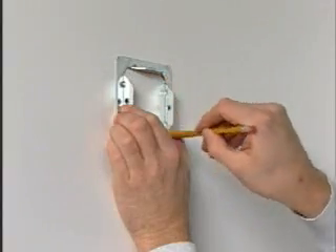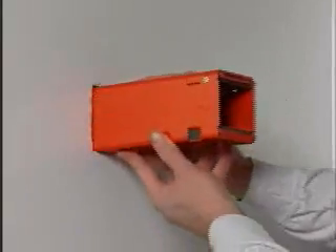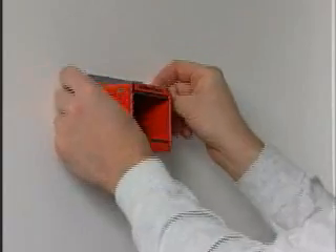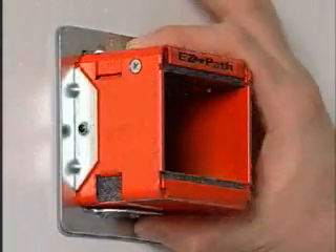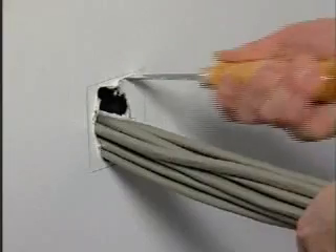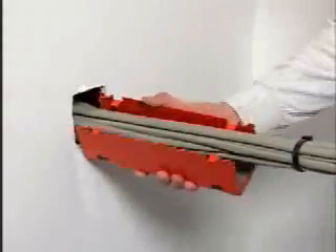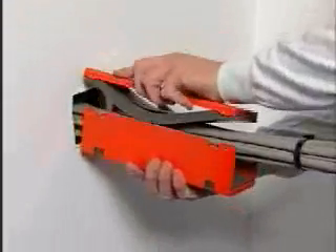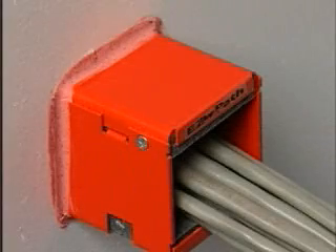EZ-Path is truly quick and easy to install. For new cable installations, the unit is slid into the wall opening and wall plates secured to the pathway with simple set screws lock the wireway in place with no mechanical attachment to the wall. When installing around pre-existing cables, the EZ-Path wireway is easily split and reassembled around the cable bundles and slid into the wall to effectively restore the fire barrier integrity.